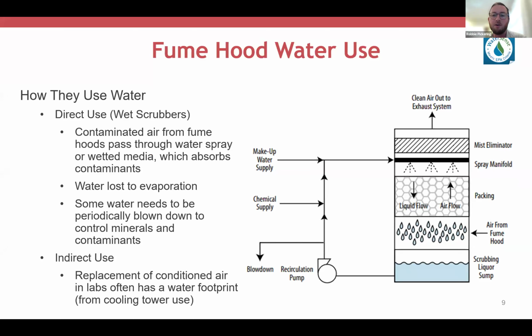If they don't have wet scrubbers, fume hoods may still have a water footprint. Many laboratories use cooling towers for equipment cooling and HVAC. When fume hoods are left open, they exhaust a significant amount of conditioned air, which will need to be replaced with more conditioned air. A lot of you are probably familiar with Shut the Sash campaigns. In exactly the same way that you can achieve greater energy efficiency by using variable frequency fume hoods or by closing your sash, labs that utilize cooling towers should also see improved water efficiency by implementing these programs.